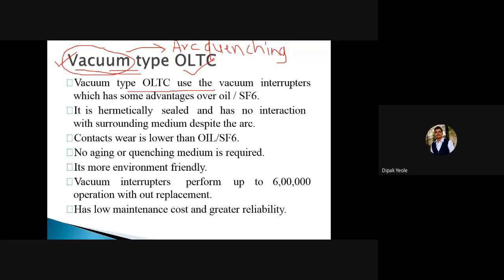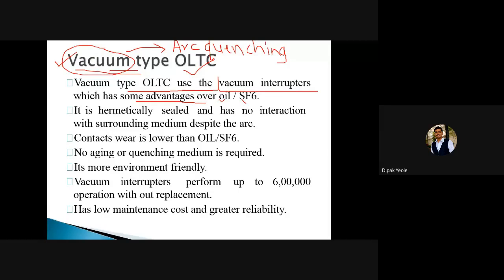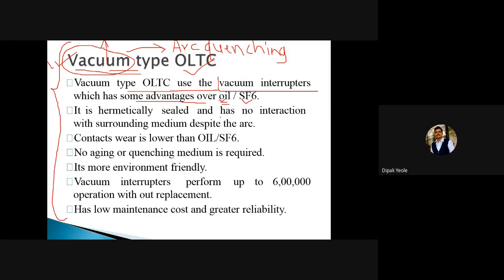This is not in your syllabus, but for knowledge purpose I am covering this part. We are always interested in using a better system. If you are using an oil on-load tap changer, obviously the oil problems are there. One can minimize those oil problems with the help of vacuum. But no doubt, the vacuum interrupters or vacuum type OLTC has a higher cost than oil. It is hermetically sealed and has no interaction with the surrounding medium. Despite the arc, the contact wear here is lower than oil or SF6.